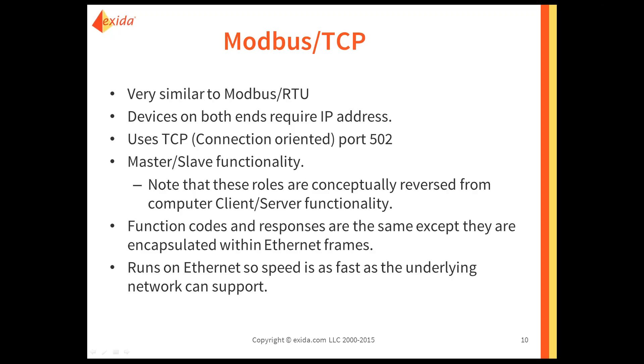Modbus uses a master-slave functionality, where the master makes a request and the slave responds to it. When working with computers in general, the master-slave functionality is conceptually reversed from what everybody is used to in a client-server orientation, where the client makes a request of the server. Keep that in mind when discussing Modbus devices on an Ethernet network versus computers communicating with each other. Master-slave in Modbus is conceptually reversed from client-server.